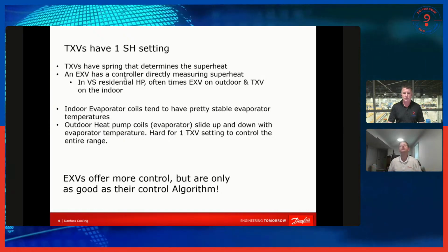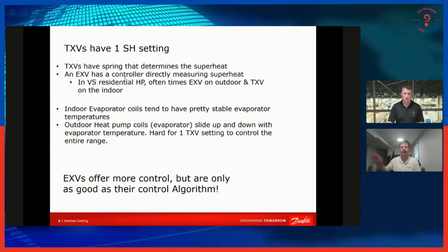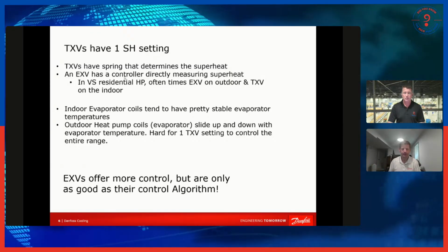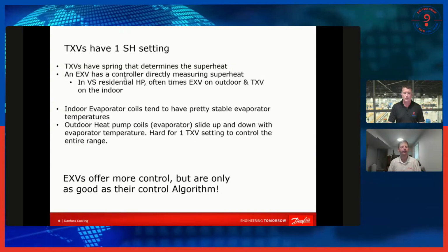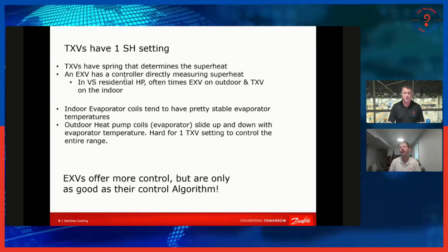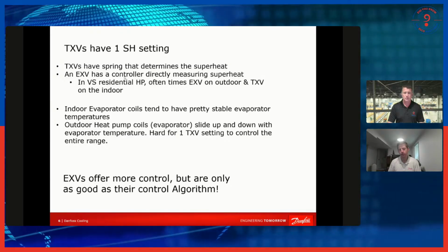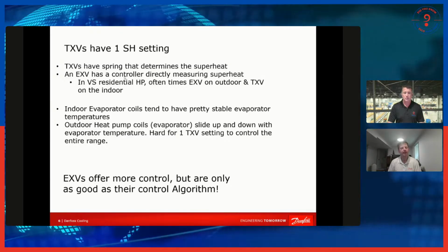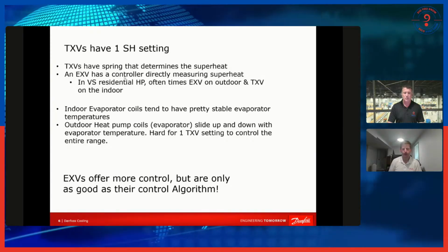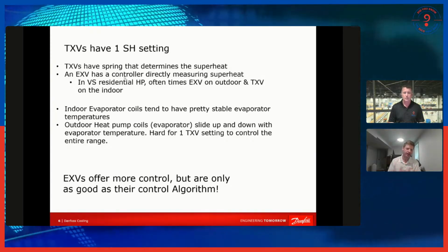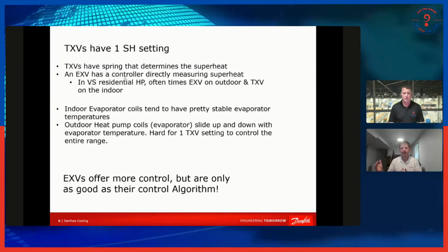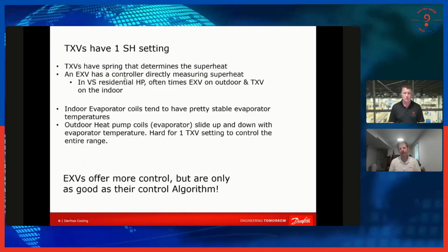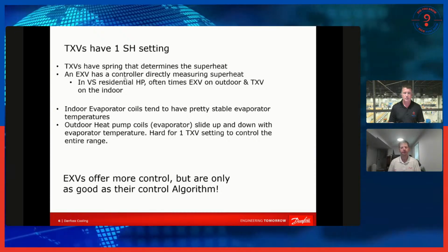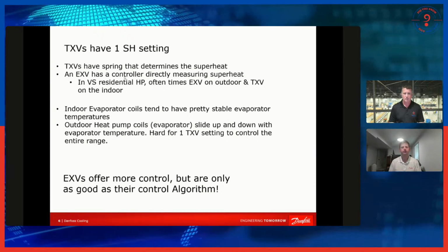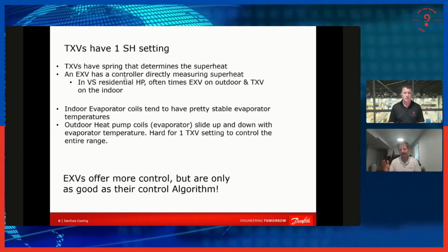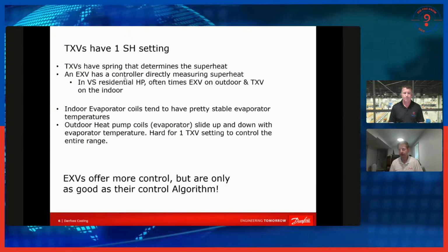You might be heating when it's 50 degrees outside. You're also going to be heating when it's 0 degrees outside. So look at that wide range in evaporator temperatures you might see on that outdoor coil. And that really gives a big advantage to an EXV, because you're directly measuring with a pressure transducer and a temperature sensor what that superheat is on that outdoor coil. And when you've got the TXV, you've got the bulb and the external equalizer, and it's measuring superheat, but it's not as precise as a digital computer can be. And you can now dial in what you want that superheat to be based on different outdoor temperatures.